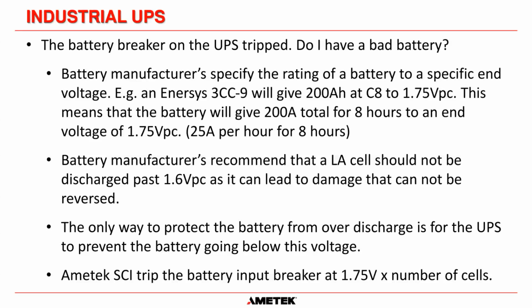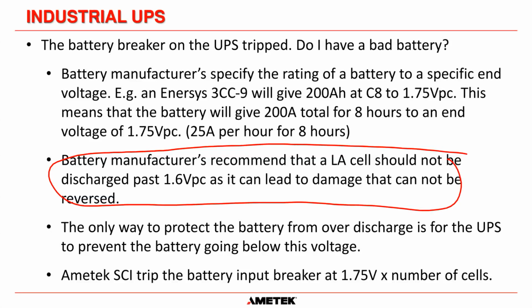The second thing is the battery manufacturers recommend that a lead acid cell should never be discharged past 1.6 volts per cell, because it can lead to damage that cannot be reversed, and that's due to sulfation of the plates. The crystals will form in such a way when you go below 1.6 volts per cell that it's sometimes difficult to dislodge those sulfation crystals from the plate, and it leads to premature failure of the battery.